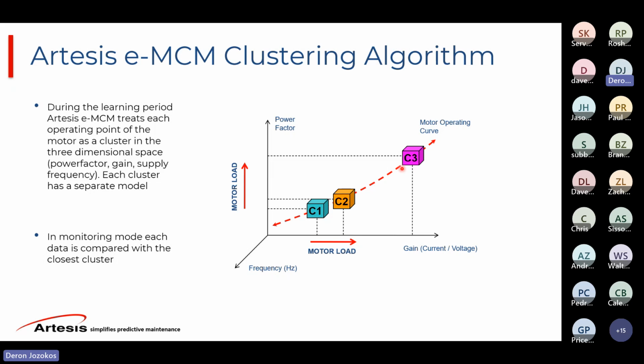So that simple system pumping down a tank on and off may only have a few dozen of these clusters, and then you have the cooling tower, which has hundreds and hundreds of these clusters. So now when it sees the VFD supplying 52 hertz to the motor, it's going to have a math model at 52 hertz to compare it to, and it won't get confused by running at 32 hertz and only having the data from 52 hertz. So it's always got a cluster to compare that data to.